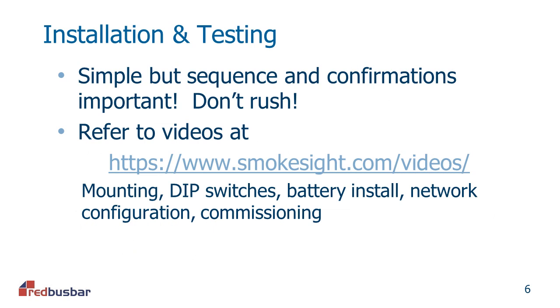So, okay, we've discussed a little bit about the overview. Let's have a look at the installation and testing side. First thing I'll say is it's simple, but don't rush it. You just need to follow the sequence and you will understand why. Now, the sequence is detailed at smokesight.com videos. So you'll see there's a separate video there for each of the smoke alarm types. The videos will go through the mounting. There's a common mounting base for all smoke alarms, so that makes life a bit easier. They also cover the dip switches that are used to either enable or disable the wireless capability or the auto test capability, the battery install and how that relates to setting up the network arrangement, and also the commissioning, the testing that you can do before you leave site to establish that the system is functional.